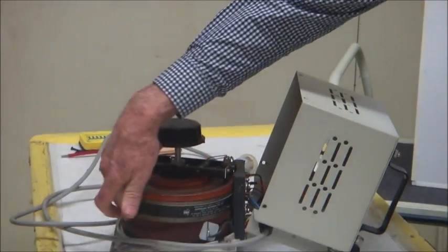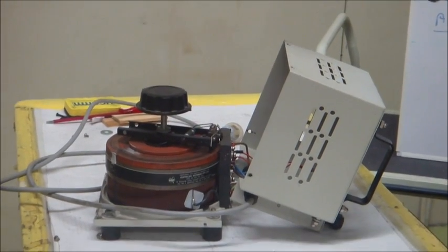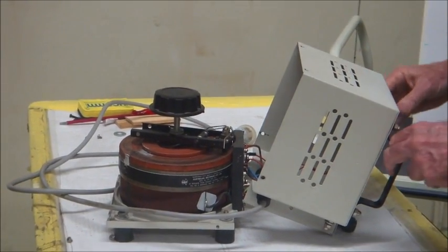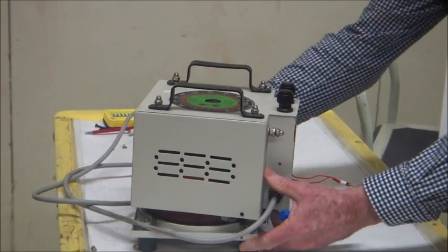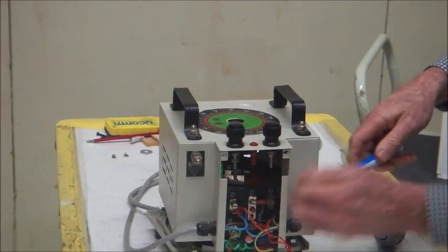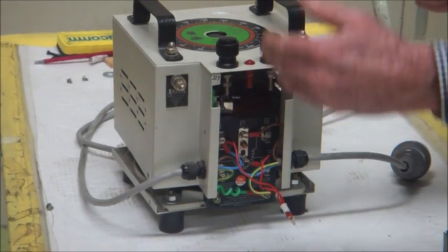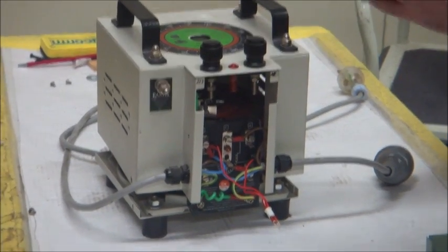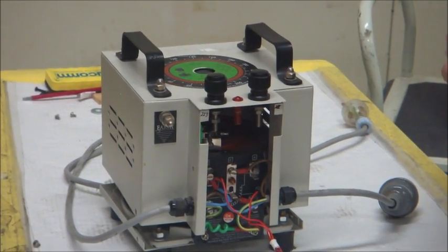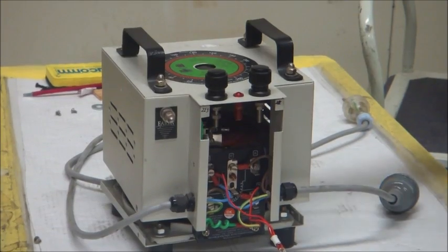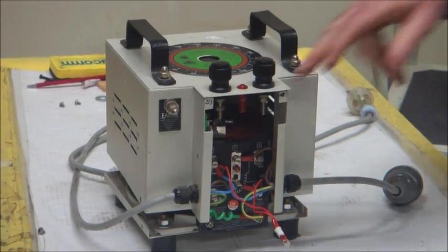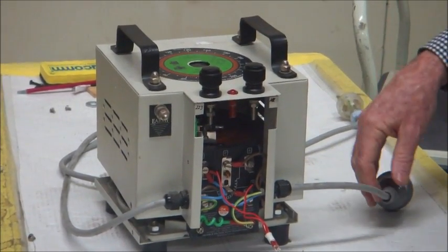This is the toroidal transformer. So this is a single phase variac and this is what it looks like. It has various connections on the inside where you can actually change the maximum voltage depending on what your input voltage is. If it's 220 or 230 or 240, you can adjust and change the taps on the input side when you set it up.